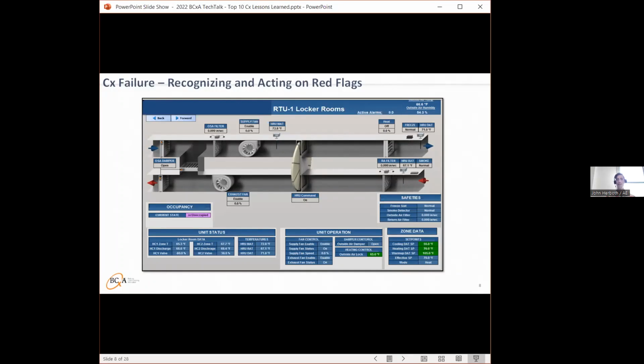And I try to make sure that gets changed quickly, because a lot of times when programmers are doing work, and you don't have somebody super experienced, or they don't know how all the field equipment is done, you have a programmer versus the field installer for a controls team, and there can be a disconnect on how that equipment is to operate. Because you look at a graphic, and especially on safeties, and you think, maybe the temp sensor is in the wrong location. That might impact how a safety operates. That might impact how equipment performs. And it really does make a huge difference.